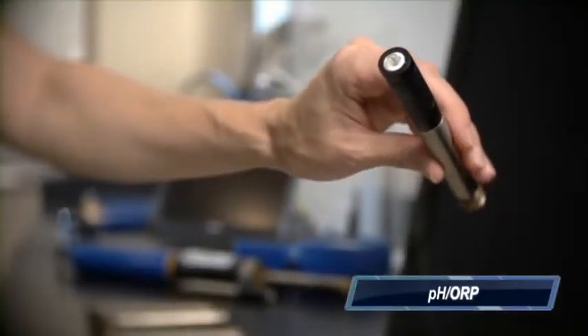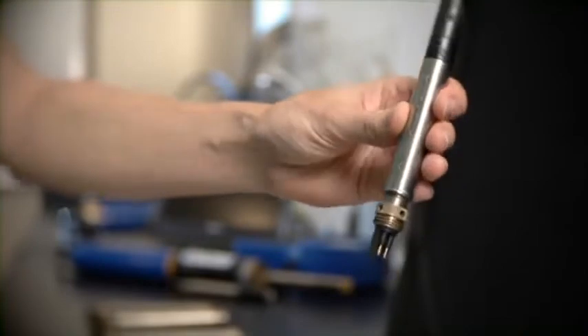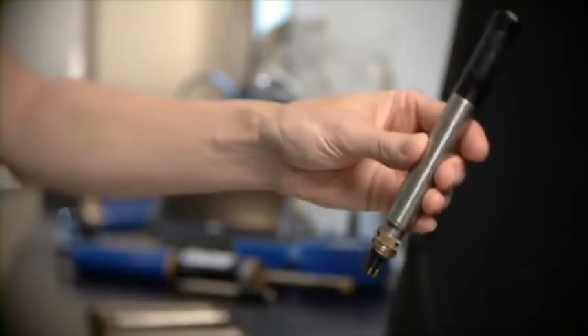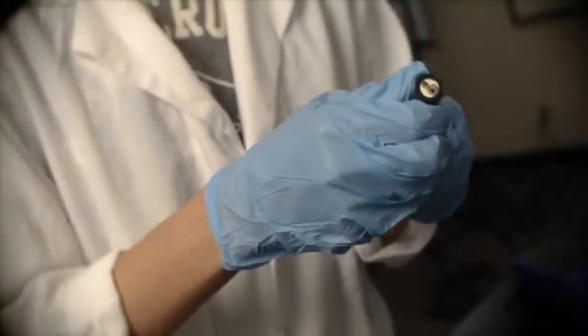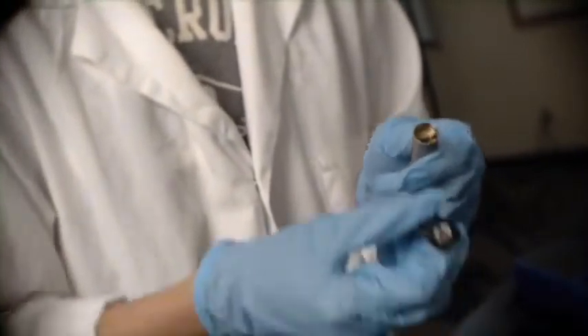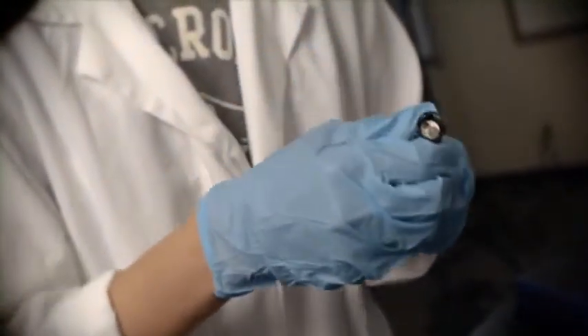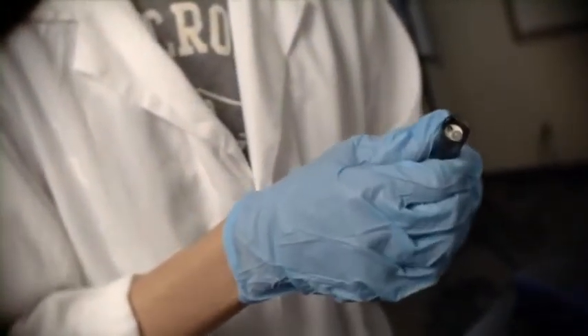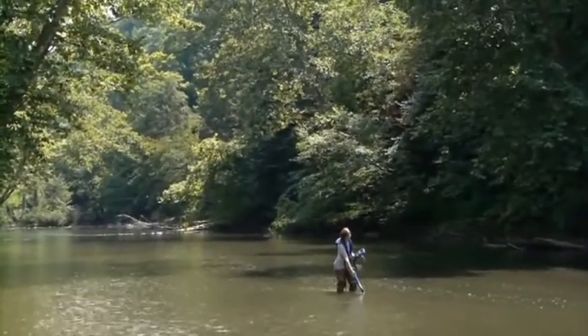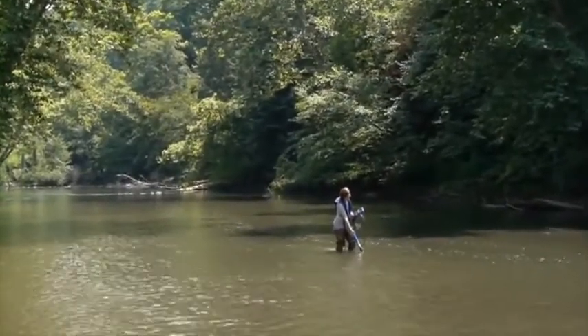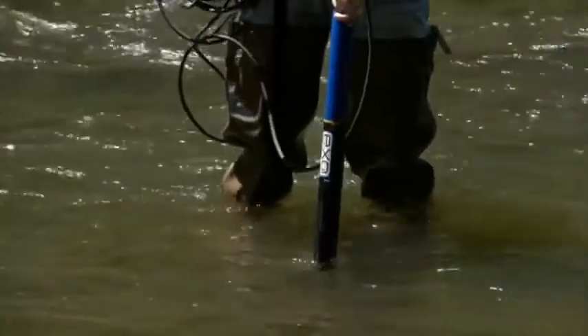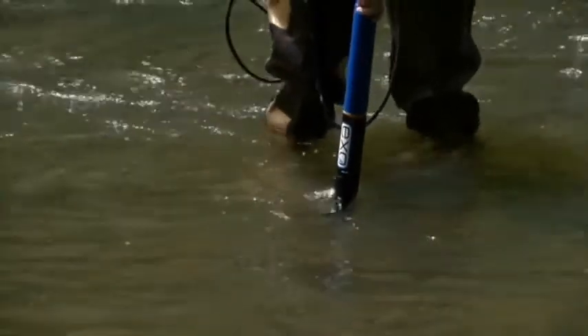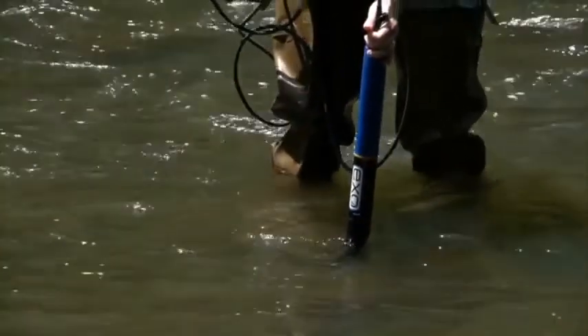pH/ORP. We've introduced a modular design to the pH/ORP probe. Once a probe's electrolytes become exhausted over time, you can simply replace the probe's tip, saving time and money. Not only will this represent a decrease in operating cost, but the pH/ORP probe is now more accurate and responds faster than previous versions, and works well in conditions such as cold and low ionic strength waters.